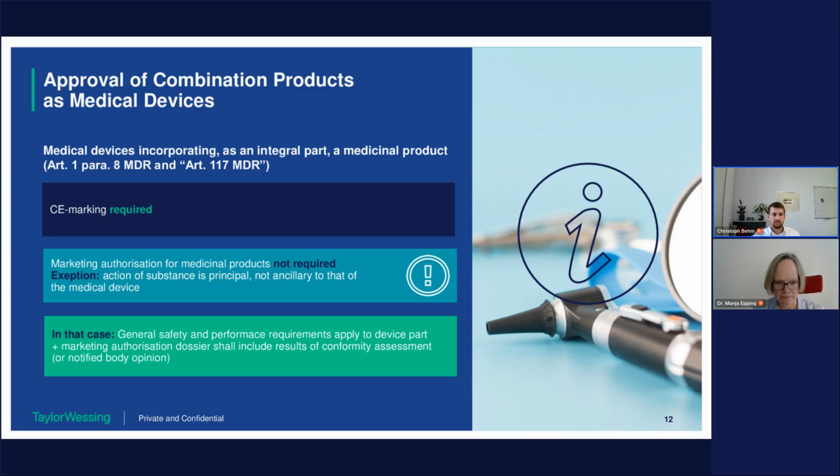Moreover, in this case, the GSPR, the General Safety and Performance Requirements from Annex 1 of the MDR, apply to the device part, and the authorization dossier for the combination product shall include the result of the medical device conformity assessment. Dependent on the risk class of the medical device, the conformity assessment has to be carried out by a notified body. That's the private body which Manja mentioned earlier.